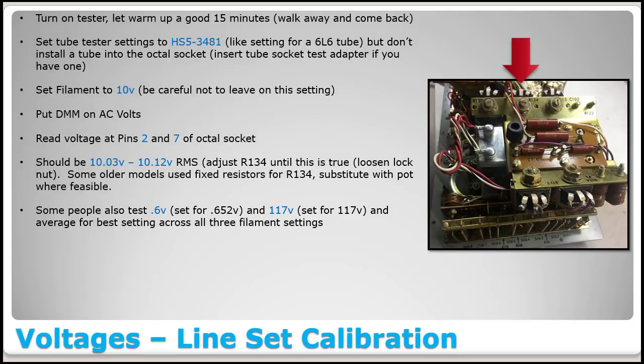And I noted here some people also test at 0.6 volts and 117 volts, the two ends of the filament scale, and just making sure that those are somewhat in range. You can adjust to get the 0.6 perfect, and then your 10.03 to 10.12 will be off a little bit, and then you swing it over to 117, you adjust to get it perfect, and then both the 10 volt and the 0.6 volt are off a little bit. It's because this is not a highly precision device, but that's why we usually try to adjust around the 10.3.